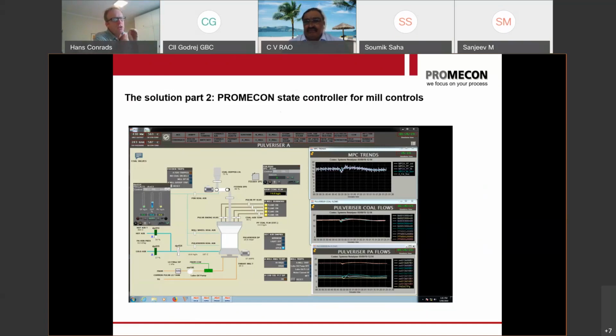If you try to smooth that signal and use it in your DCS system, this is very difficult. For this reason, Promecon has designed a new state controller, especially for spindle mills, which can give you a feeder demand signal to control your mill output in real time.